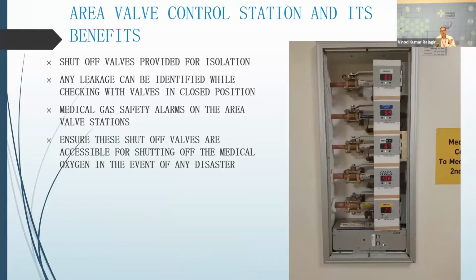For the medical gas system, we also need to see how important the distribution into the critical areas is. We specify that we should go for area valve stations, control stations, which are mandatory for any critical areas. Why? Because these systems have shut-off valves which can be used in isolation, and they also have indications of the amount of gas that has been consumed. If there are any leakages, you can check them. It has inbuilt alarm systems, which are also mandatory for the people handling those areas. And of course, when there is a fire, you have the shut-off valve to shut off the oxygen so that the disaster is much reduced in case of an evacuation. So the area valve control station becomes an important link to the area which gets the gas in that critical space.